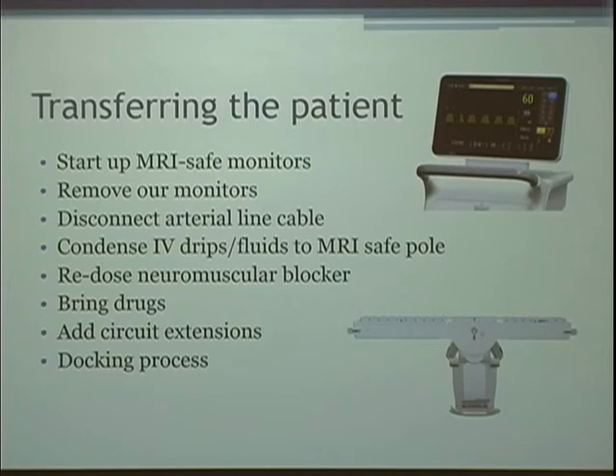You start up your MRI safe monitors. They'll be displayed on a portable monitor that you can wheel alongside the patient that looks just like this one on the screen. We pull all of our monitors off. As I said, our devices are not safe for the MRI scanner. So that means the EKG leads. Our blood pressure cuff can stay on this patient, but you have to remove the cable and pull the sticky pulse ox off the patient.